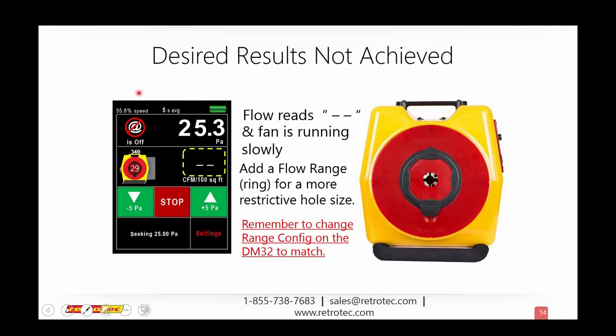So I have reached 25, and this is my fan speed. My fan isn't really working that hard, so I have pretty easily reached pressure. But I'm not getting any reading at all in channel B. And channel B is telling me the amount of flow, the CFM. That's the amount of flow that's going through the walls of that ductwork. But the problem is, in reality, that ductwork is so tight that there's not enough air moving through the fan for the fan to physically register an amount of flow.